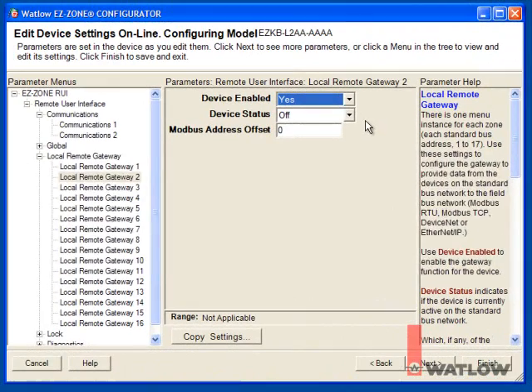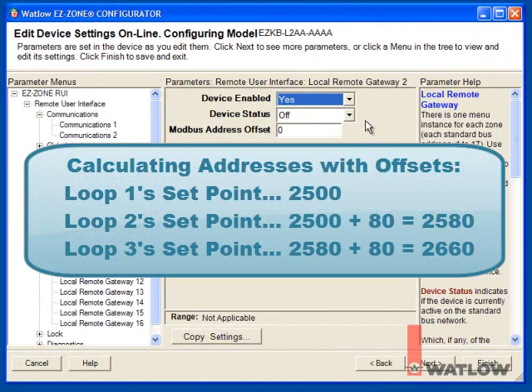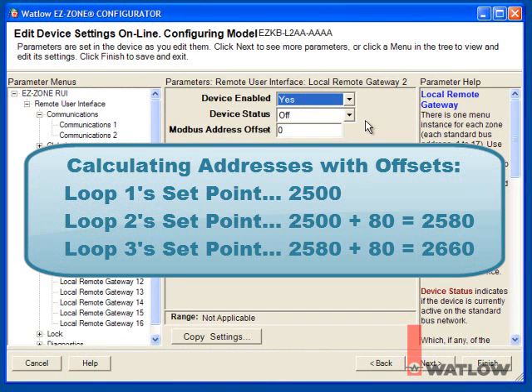so the address for the second loop's closed loop set point is 2500 plus 80, 2580, and the address for the third loop's closed loop set point is 2580 plus 80, 2660. To be able to access the closed loop set point for loop 3 in the first RM control module, we must offset the second control module's Modbus addresses by more than 2660.